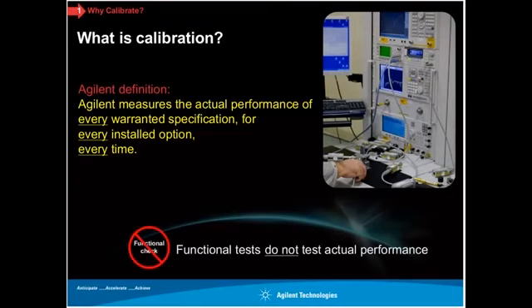Many people in that first use case — just meeting ISO 9001 — say they're getting calibration functional tests and think that's sufficient. But functional tests do not test actual performance. That's an important distinction I want to make clear.